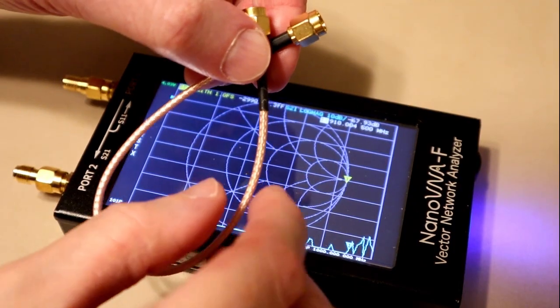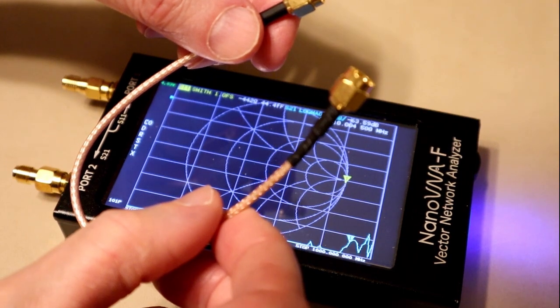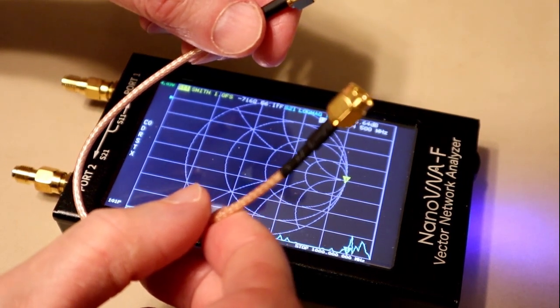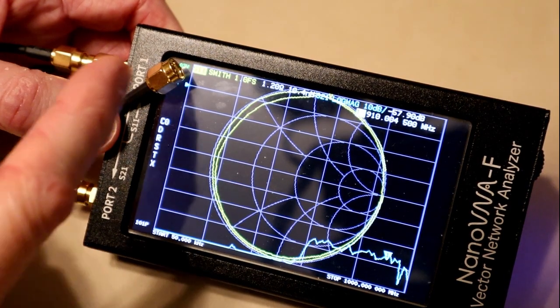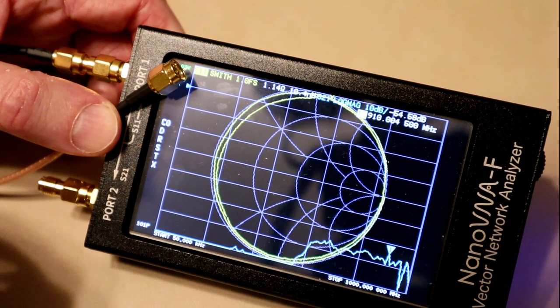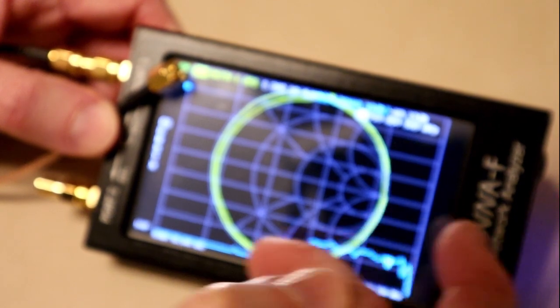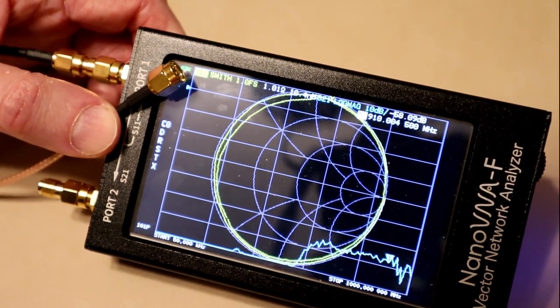But let's watch what happens when we attach a cable onto here that was not present when we did the original calibration. For this, I'm just going to use one of the original 20-centimeter cables that comes with the VNA. And I'm going to attach it to port 1. The cable is still an open circuit, but now the point is not over at the right-hand side, at least not at all frequencies. It's instead anywhere on the chart. It's wrapped around the chart several times.